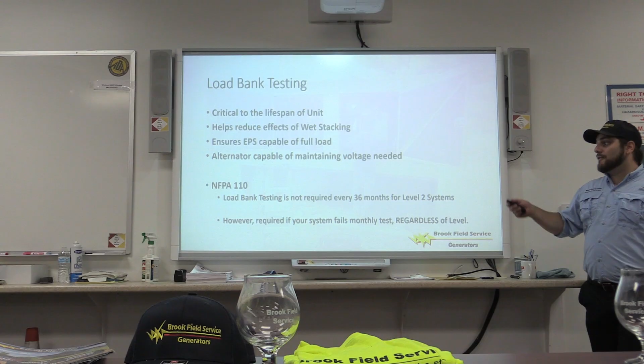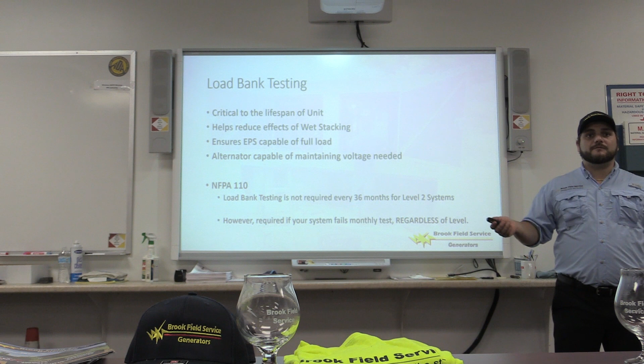So again, just making sure that your diesel system can even run what it's rated for, which after a period of time can deteriorate. And the alternator, making sure the alternator is capable of maintaining the voltage needed. NFPA 110 says that load testing is not required every 36 months for Level 2 systems. However, if your system fails a monthly test, it is required. So again, just making sure that you are abiding by those regulations.